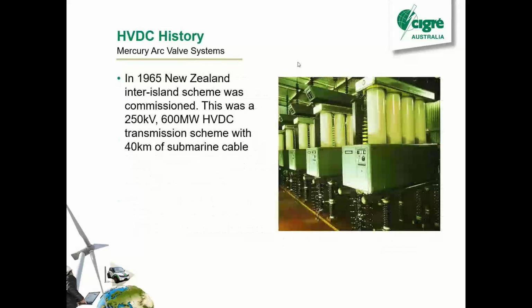I had to put a plug in for the New Zealand scheme, of course. In 1965, the New Zealand Inter-Island scheme was commissioned. This was a 250 kV, 600 megawatt scheme, so you can see it's quite a big step up in the power and the voltage. The New Zealand scheme wasn't the first scheme, but it was one of the first big schemes. And we've got a 40 kilometer submarine cable, and that was a bipolar scheme using these mercury arc valves.